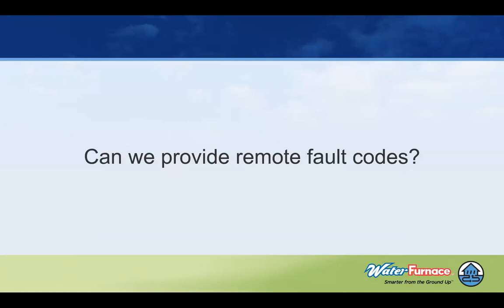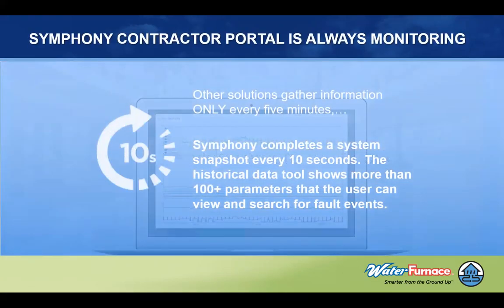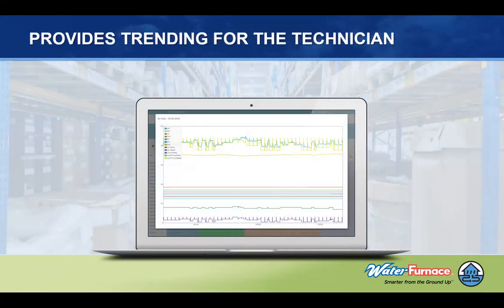So how can we provide remote fault codes and service for the equipment before we travel? Behind Symphony is a database of 100 parameters on average per system, and that varies from the base controls all the way up to an advanced controls variable speed system, that we capture every 10 seconds to make sure that we catch anything that's going on with the system, and we can then monitor what's going on. We can provide trending for each system to know exactly what's going on within that system. And each of those parameters can tell us what in the system is operating at a component level.